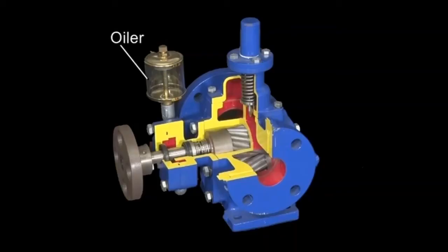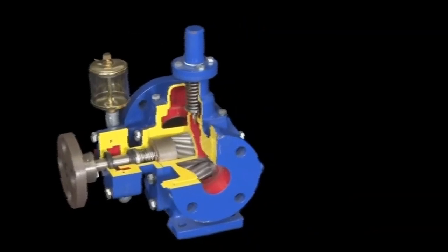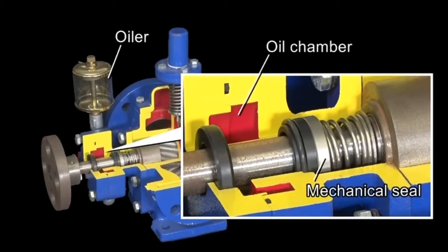An oiler is attached to gear pumps and three rotor screw pumps. With the oiler, an oil chamber is provided on the atmosphere side of the mechanical seal, into which lubricating oil is sealed to cut the atmosphere off the sliding surface. This prevents fuel oil leaking out of the mechanical seal from solidifying. Replace lubricating oil if it has discolored and the oil level has risen beyond a specified level.